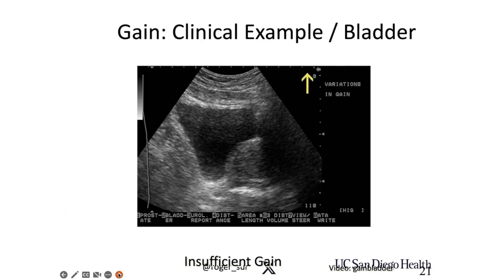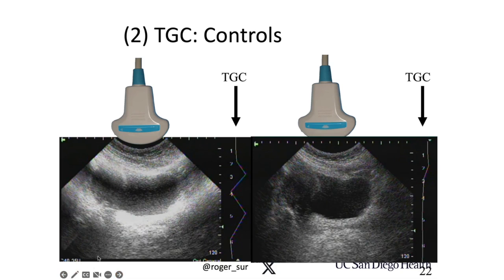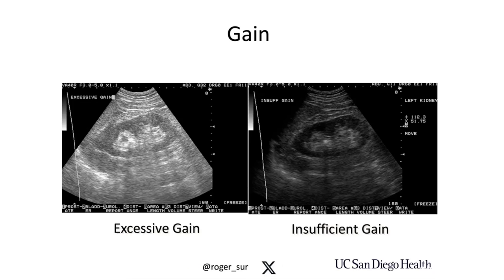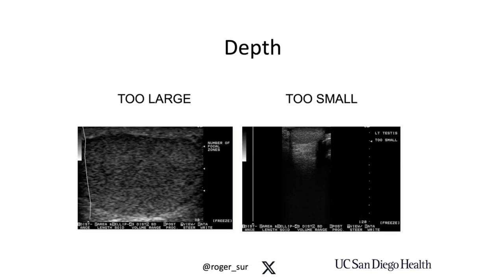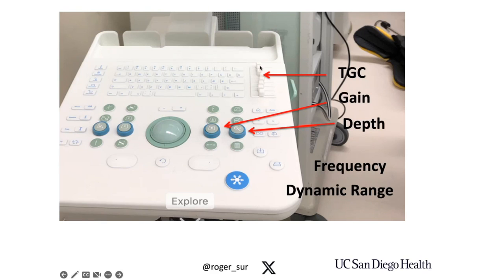The other aspect I want to talk about is the TGC. It's right here—these funny looking buttons. It's really important before you start your ultrasound to always look at the TGC, because just like the depth, your previous user may have messed with these buttons, changing what your picture looks like. Basically, the TGC is the gain for each level of the monitor. This button controls the lower part of your monitor, and this one up here controls the upper part—each button corresponds to a certain horizontal portion of your image.